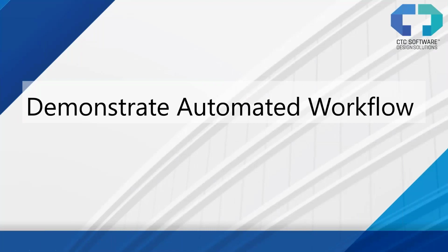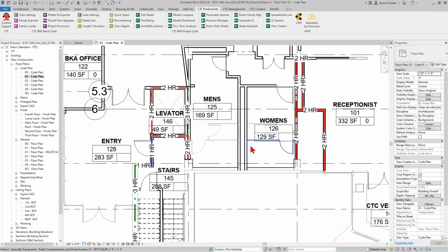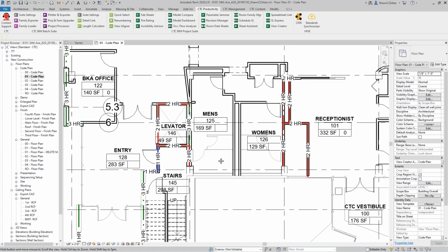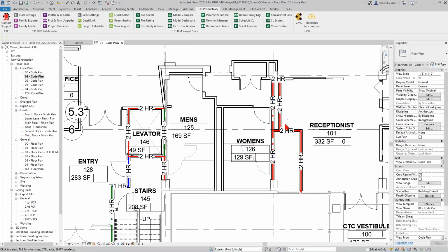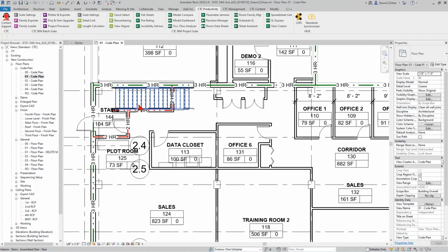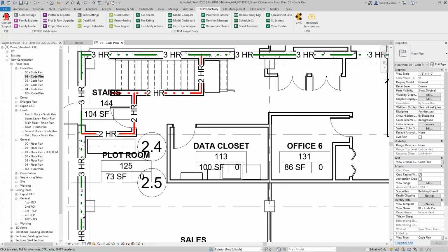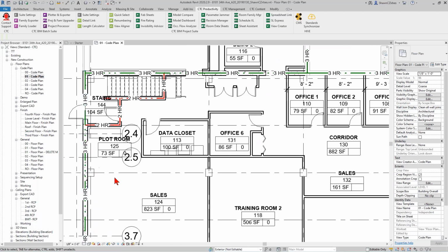And now I can quickly, did I just close all of Revit? No, I just closed the tool and it happened to refresh forward. So now I can quickly see here, like around these shaft areas, there's some 2 hour walls. There's 2 hours around this vertical shaft. There's a 1 hour wall here, dividing off this stair entry. At the back of my building over here, there's a number of 2 hour walls around these vertical shafts, since this is all vertical circulation and this is sort of attached to that, plus a 3 hour wall here on the exterior of my building.